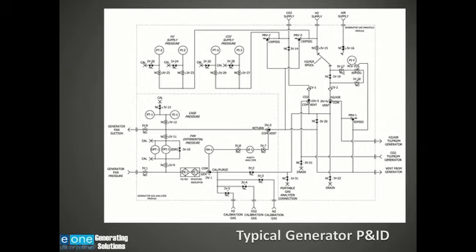Some plants will choose not to use this, and they'll shut off these isolation valves, and they will manually cap off the pressure, meaning an operator will go down there periodically when they get a pressure indication over here. When that drops below a certain point, they'll come open this valve and feed hydrogen into the generator. We have some pressure relief valves that go to the case so that we don't build up too much pressure in the case. This particular one is set at 65 psi, although we're maintaining a pressure in the case at 60 psi.